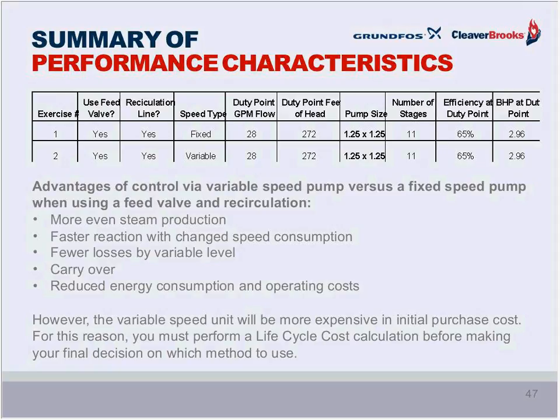In both cases, we had to use feed valves and a recirculation line. And that means that based on the process for selection, they both require the same flow and head characteristics. So we can use the same 1.25 inch suction and discharge pump, 11 stages. They both operate at the duty point, in other words, full flow, at 65% pump efficiency. And both of them put a brake horsepower load on the motor of 2.96, almost 3 horsepower. So if they both give exactly the same performance at that design duty point, why would you want to spend more money on a variable speed unit? Why not just buy the fixed speed unit and forget it? And after all, the control mode with the fixed speed motor is the most commonly installed type. So why not just stay with that?